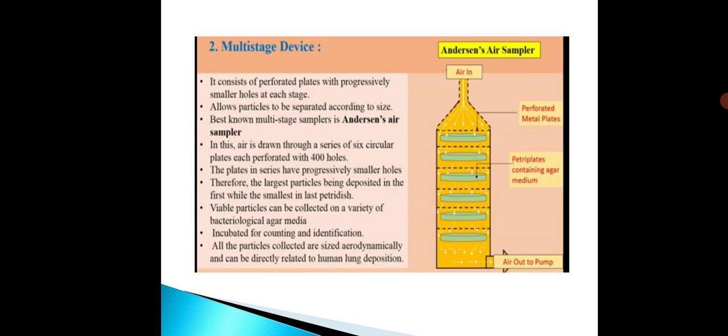Viable particles can be collected on a variety of agar media, incubated for counting and identification. All particles collected are sized aerodynamically and can be directly related to human lung deposition. On the basis of size, microorganisms settle onto the corresponding petri plate — largest particles settling first and smallest settling last. These plates are then allowed to incubate, and after incubation, colony counts are performed. On the basis of size, we can distinguish the microorganisms.